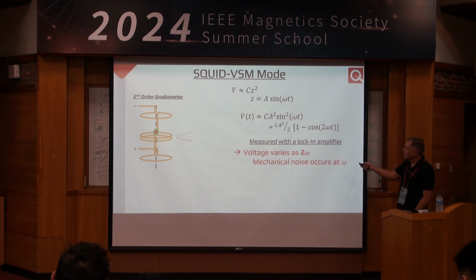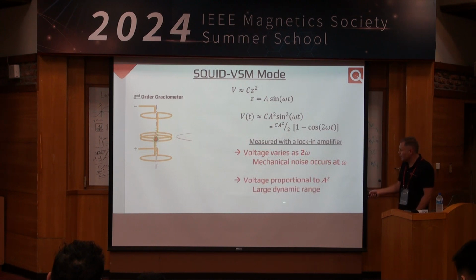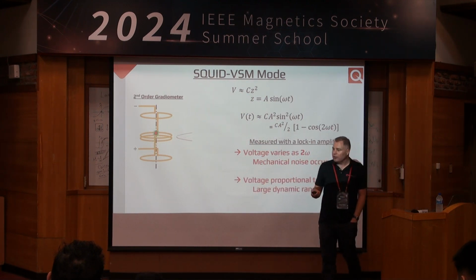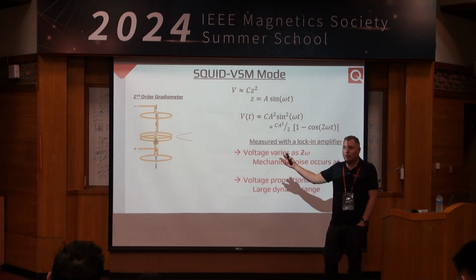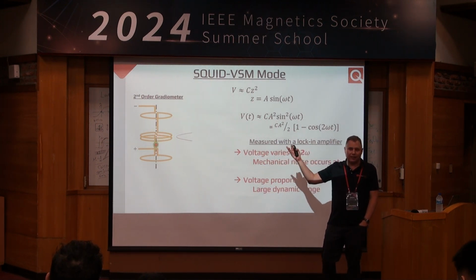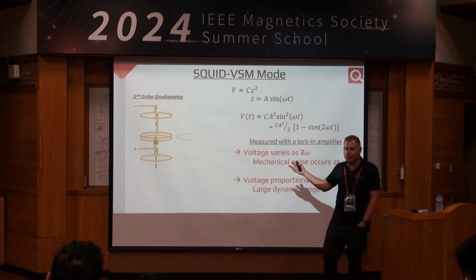The other interesting thing is that the voltage depends on the amplitude squared of the oscillation. That means we have an enormous dynamic range with the SQUID VSM mode. We can measure all the way from nano EMU levels all the way up to 100 or 1,000 EMU. So that's 10, 11 orders of magnitude in EMUs.